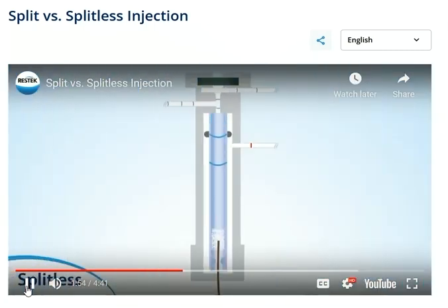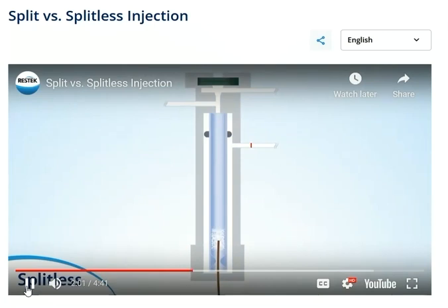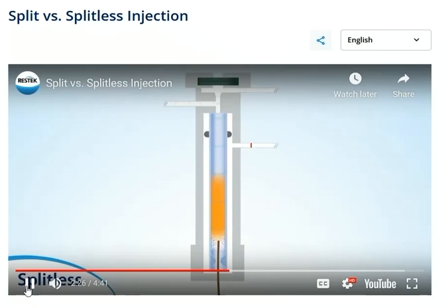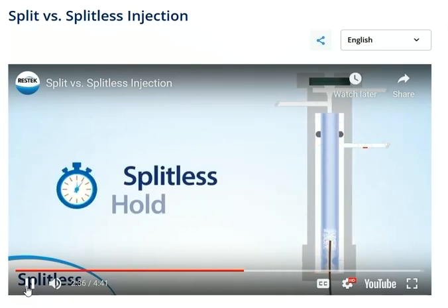Now let's look at an example of a splitless injection. In a splitless injection, the split vent is closed and left closed before and during the injection. As there is no split flow, the total flow is set at a dramatically reduced flow rate — here it's only 4 mils per minute. 3 milliliters per minute passed through the septum purge while the remaining 1 mil per minute entered the column. During injection, the sample remains within the liner for longer before entering the column due to the lower flow rate. Once sufficient time has elapsed after injection, the split vent opens to purge the inlet. This duration, known as the splitless hold time, is calculated to be long enough to allow the maximum vaporization and transfer of analytes to the column.